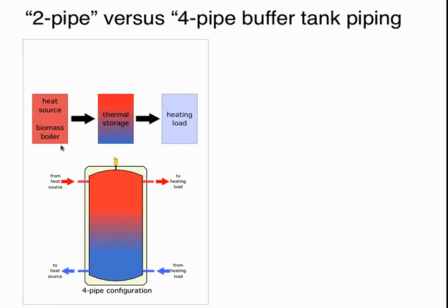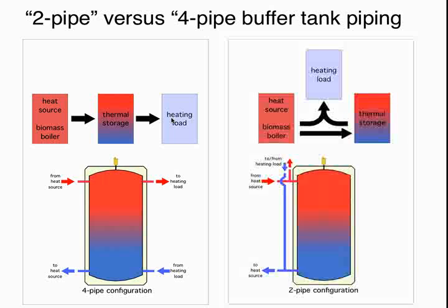And if we look at the energy flow in this situation, we're starting with some kind of a heat source. It could be a biomass boiler, it could be any kind of a heat source. We're putting all the heat that is being produced by that heat source into storage, or at least passing it through the thermal storage, and then extracting it from thermal storage and sending it off to the load. All right, so it's kind of a sequential or series relationship there between heat generation, thermal storage, and load.